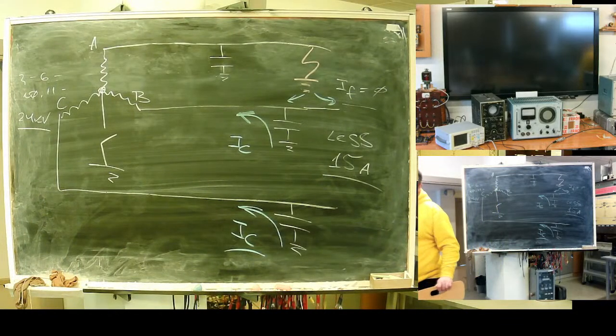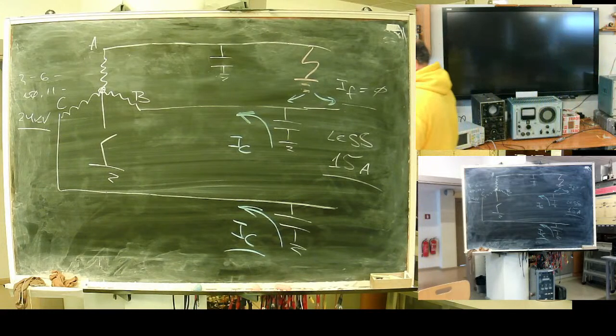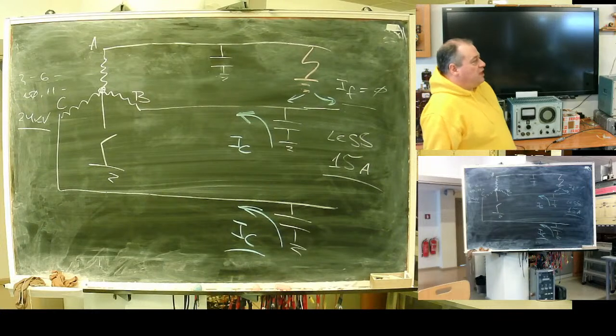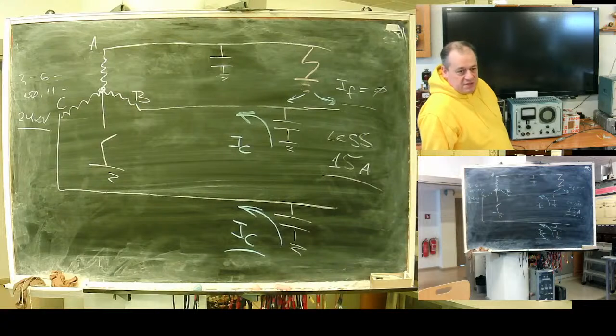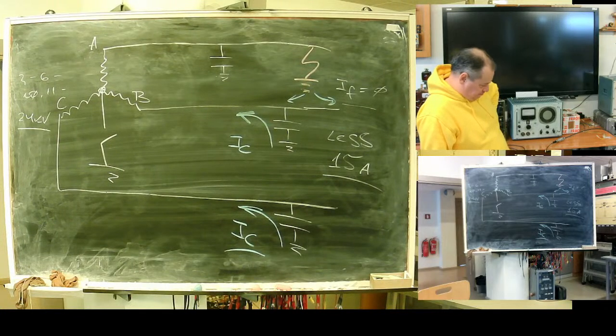Ideas, your insurer. Your insurer will push you to install protection against this fault. Actually, if fault current is small, it can wait until we have personnel. It's not dangerous for the network, but it's dangerous for humans. In uninhabited areas, not a problem, it can wait. In areas where someone can touch this wire, someone's life can become a subject of electrocution.